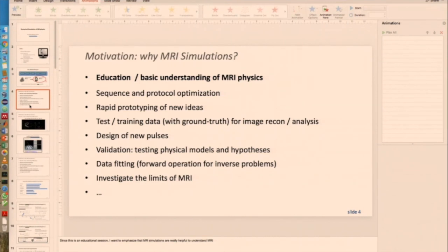And it basically follows the same checks Siemens IDEA follows. So you cannot easily exceed SAR limits, for example, but you could easily do some nasty things with respect to mechanical resonances of the gradient system, which is not well checked for in Siemens. But that's more a problem of Siemens, I would say, than of Pulseq.